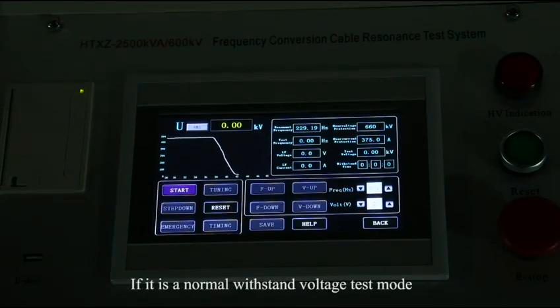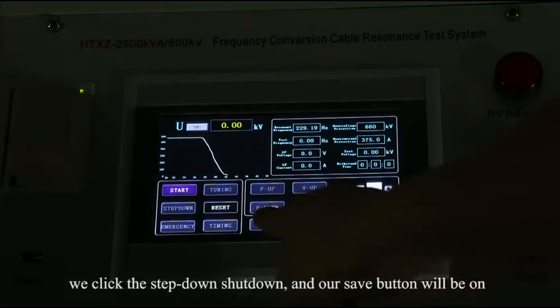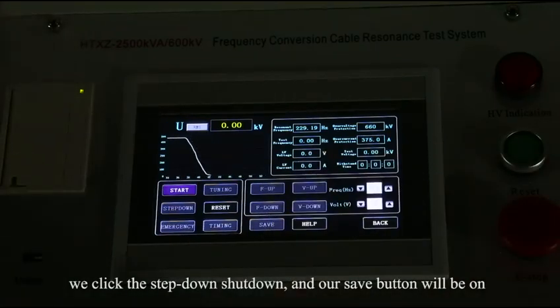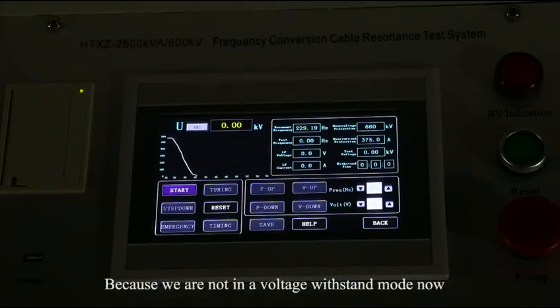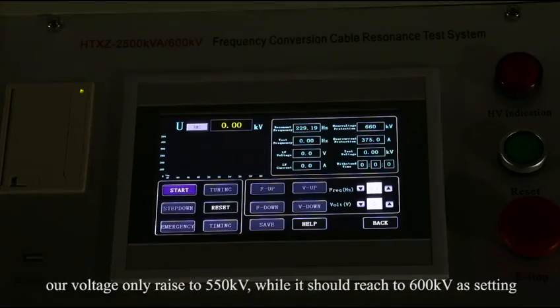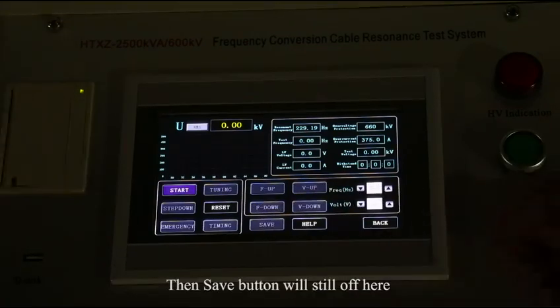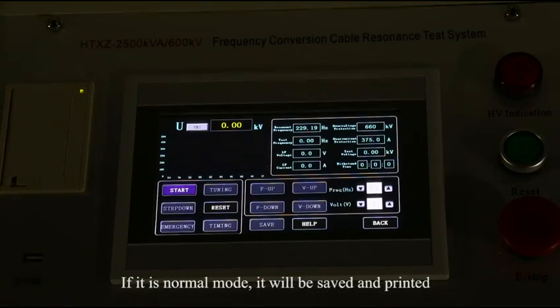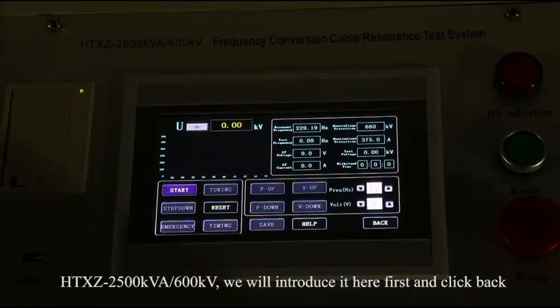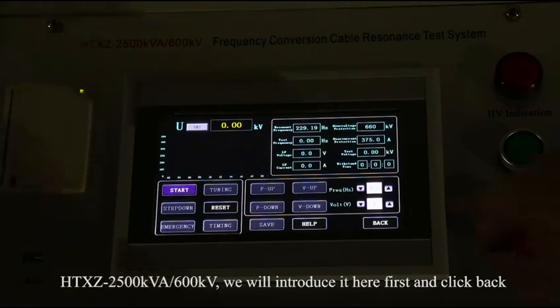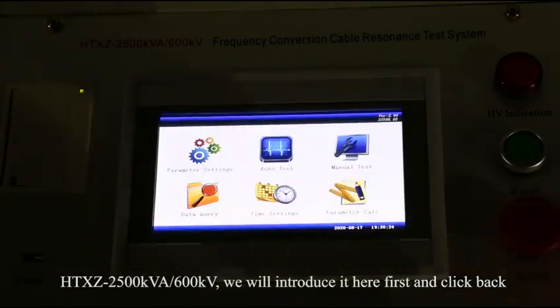If it is a normal withstand voltage test mode, we click the Step Down Shutdown, and our save button will be on. Because we are not in a voltage withstand mode now, our voltage only raised to 550 kV, while it should reach 600 kV as set. The save button will still be off here. If it is normal mode, it will be saved and printed. HTXZ 2500 kVA and 600 kV. We will introduce it here first and click back.